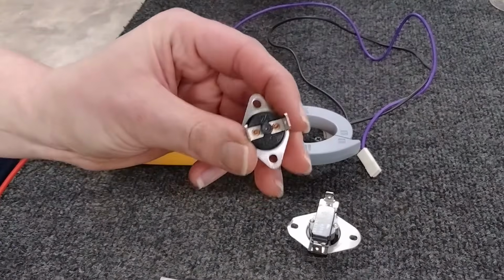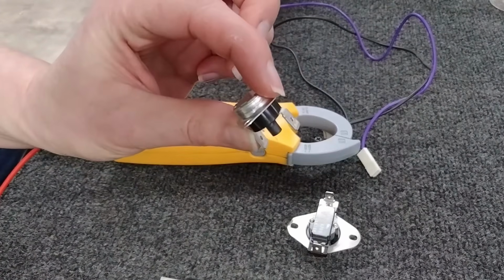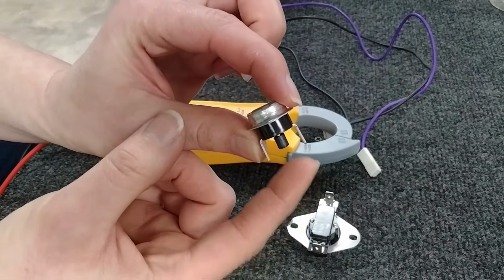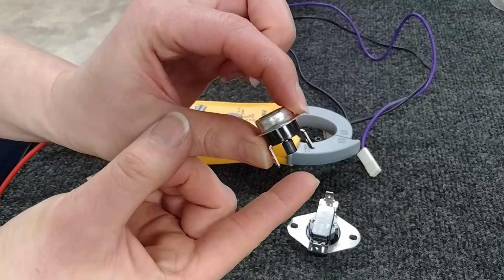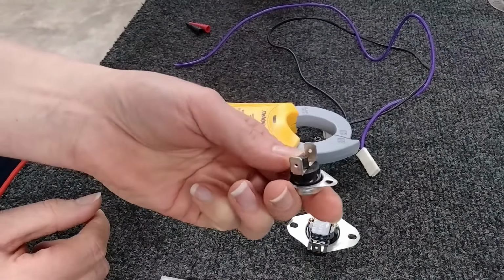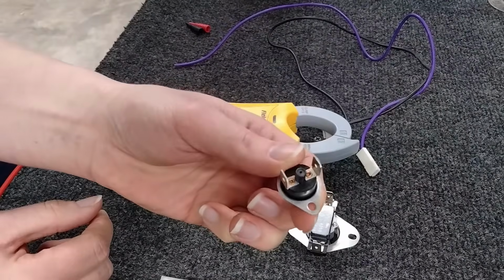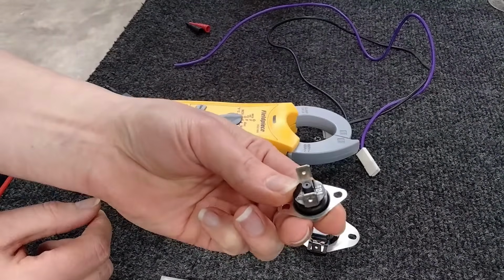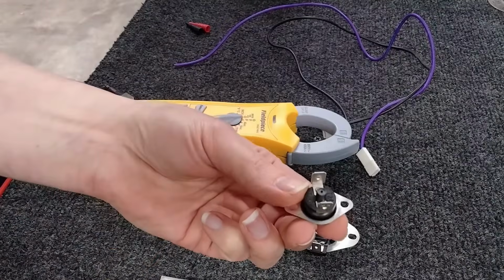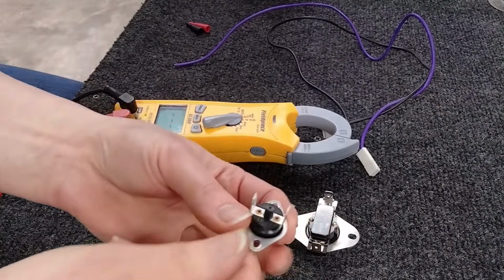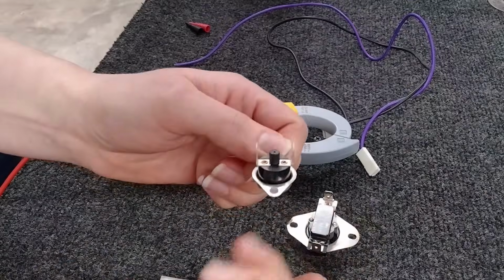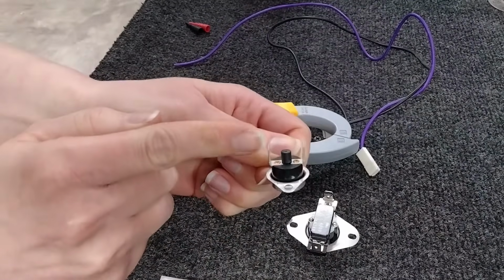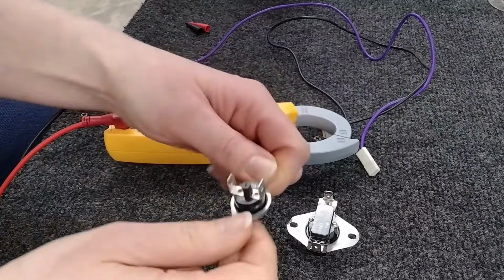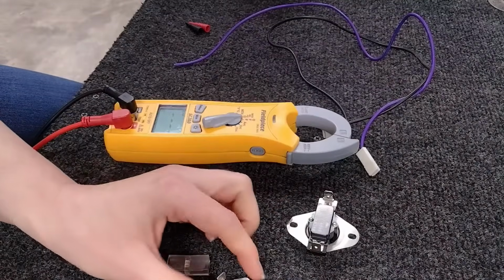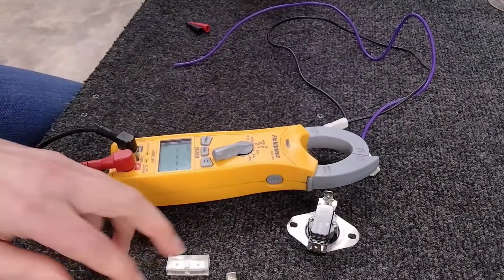This one is what we call a rollout switch, which, as you can see, has that manual reset button right there. These are near your burners, and the job of that is if you get flame rollout, which is an indication of a crack in your heat exchanger, no bueno. When that happens, it's going to cause this to overheat, and that button's going to pop. But right now, what it should be doing is getting continuity with little to no resistance.